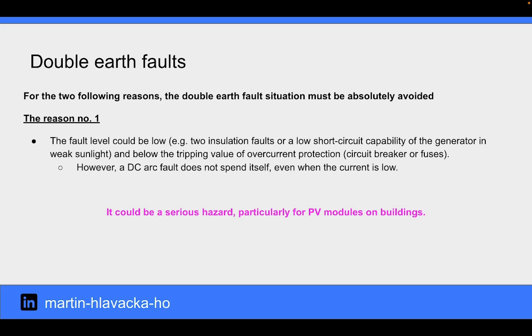For the two following reasons, the double fault situation should be absolutely avoided. The fault level could be low, and below the tripping value of overcurrent protection. However, a DC arc fault does not spend itself, even when the current is low. It could be a serious hazard, particularly for PV modules on buildings.